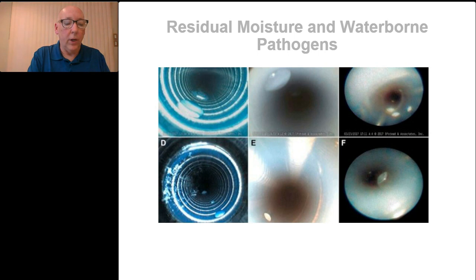Earlier we spoke about towel drying devices as well. Well, not so good for lumen devices. So what we have to do is use mechanical drying techniques to evaporate moisture. We talked about evaporation, and reduce the known adverse consequences of moisture. So if you take a look at those lumens and those water droplets, we're going to need to affect something so that they dry. Air drying is just not going to dry those in a very short period of time. It could take hours or days to render those lumens truly dry.